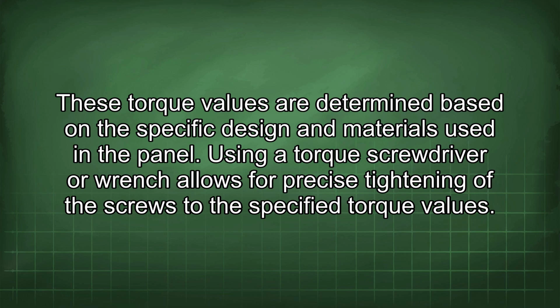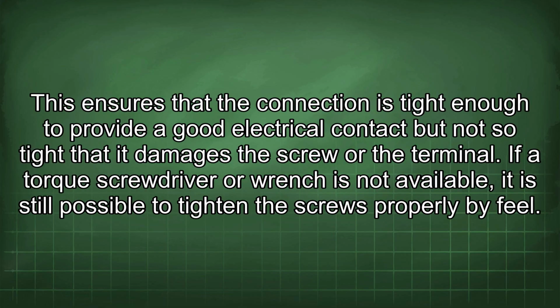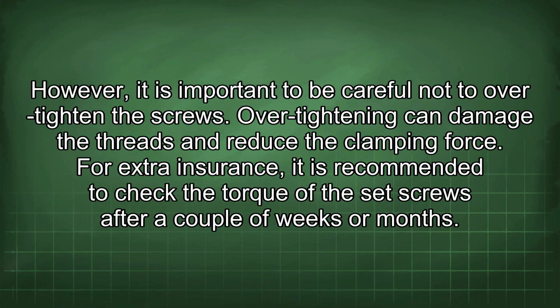Using a torque screwdriver or wrench allows for precise tightening of the screws to the specified torque values. This ensures that the connection is tight enough to provide a good electrical contact, but not so tight that it damages the screw or the terminal. If a torque screwdriver or wrench is not available, it is still possible to tighten the screws properly by feel. However, it is important to be careful not to over-tighten the screws. Over-tightening can damage the threads and reduce the clamping force.